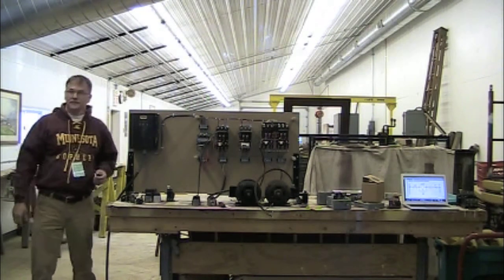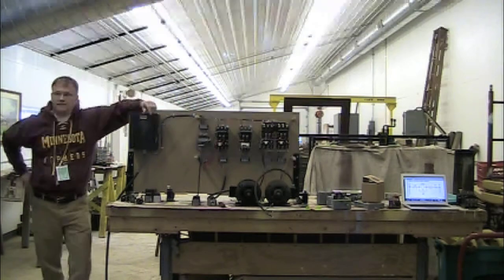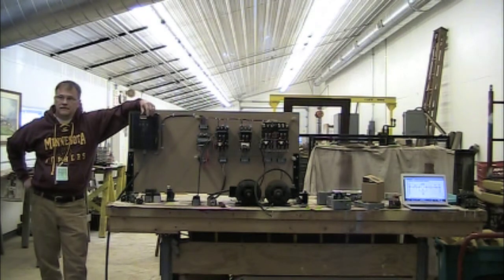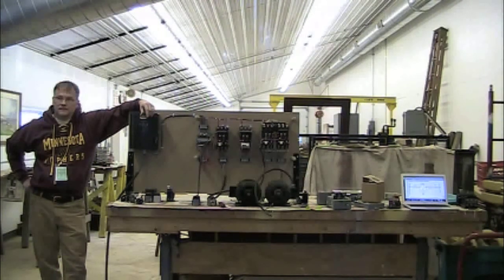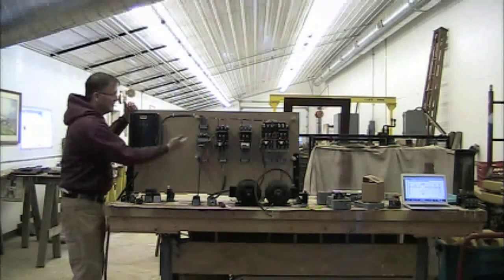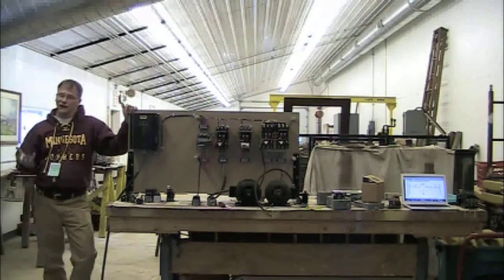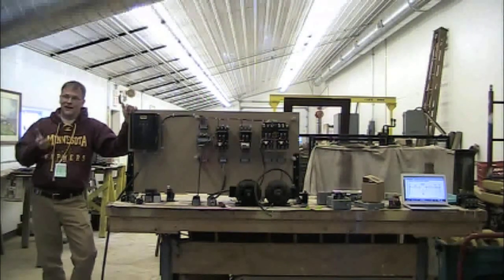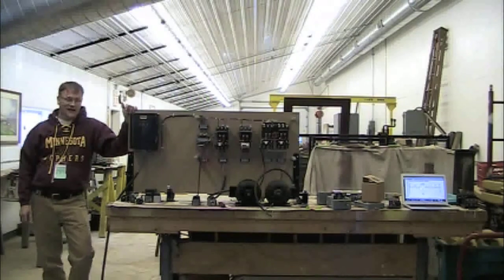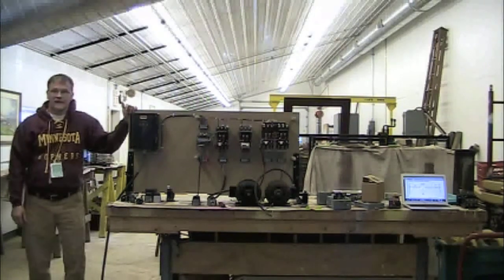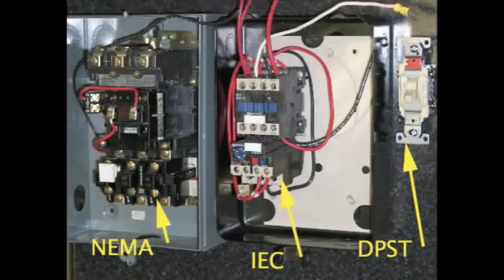Hey, Ray, so there was something going around the internet a few years ago where somebody said they had a table saw with a mag starter on it. They dropped a piece of wood and it hit the starter itself, not the start button, and it started the motor. It could. If you jarred this hard enough, it doesn't take much to lift that up, and it closes a set of auxiliary contacts, and it holds it shut. I do think that was an IEC starter. Right. Yeah. That would make more sense. Those are more prone to that anyway. Yep. The cheap ones are really prone to that.